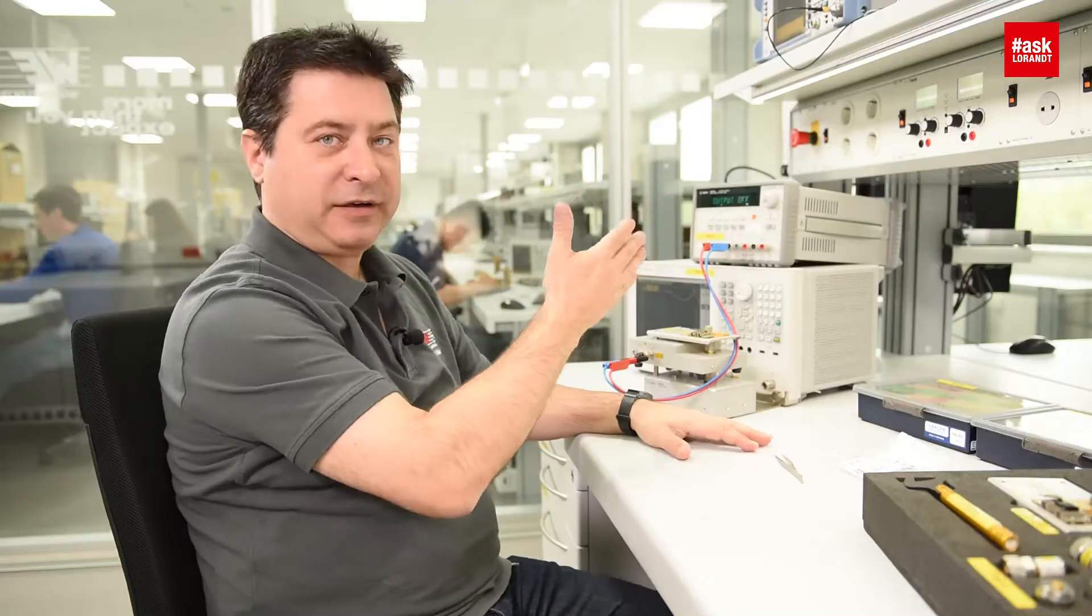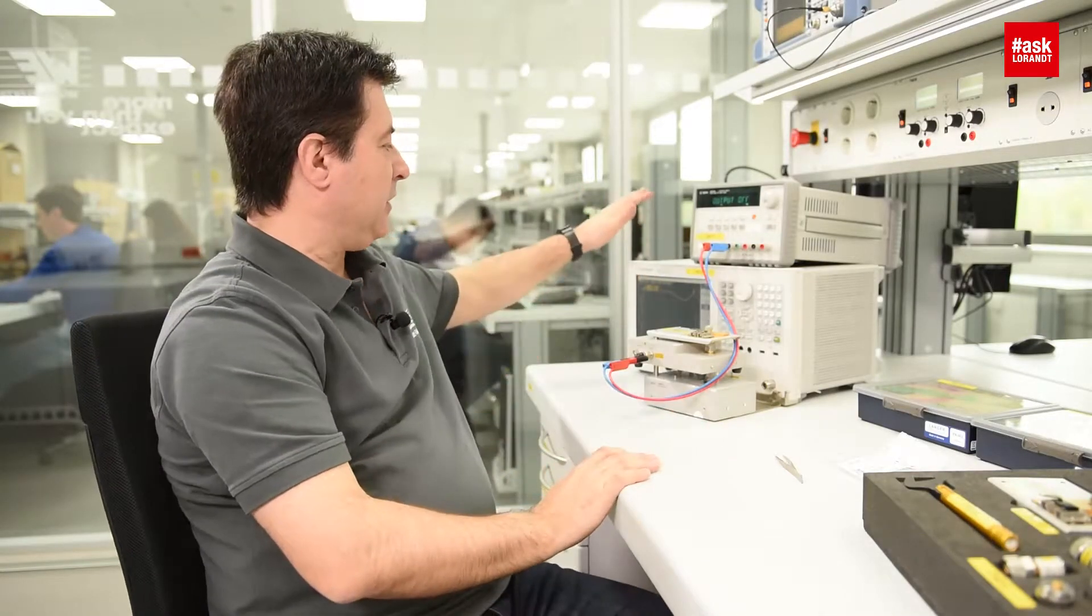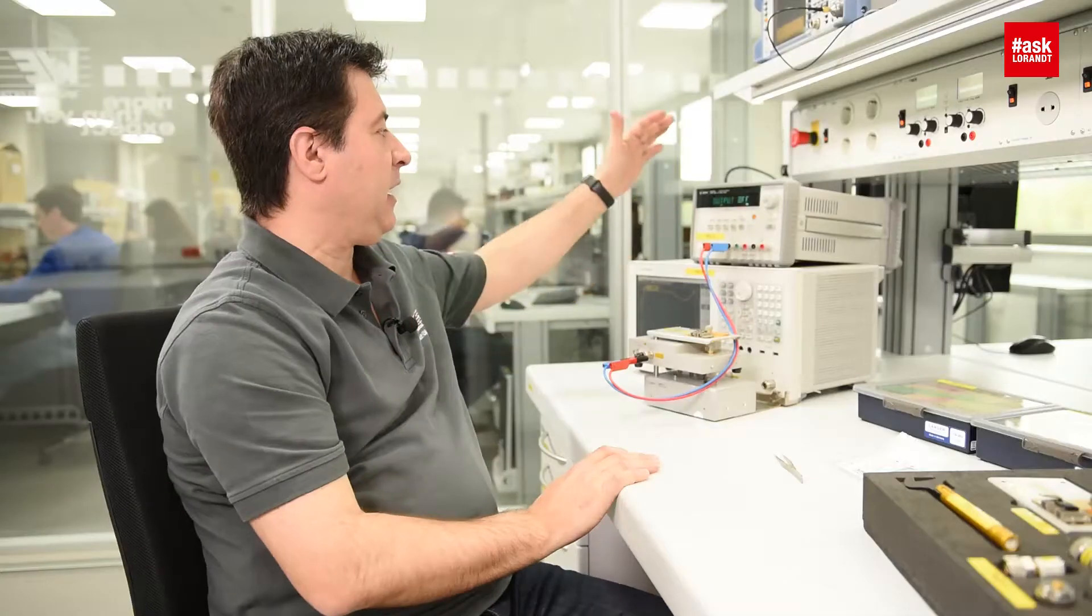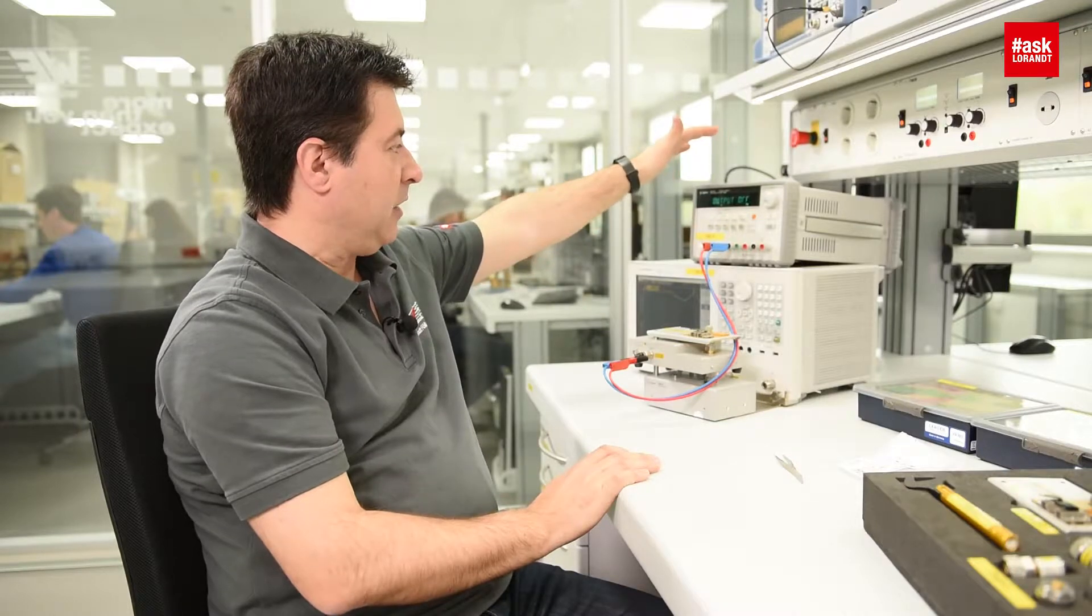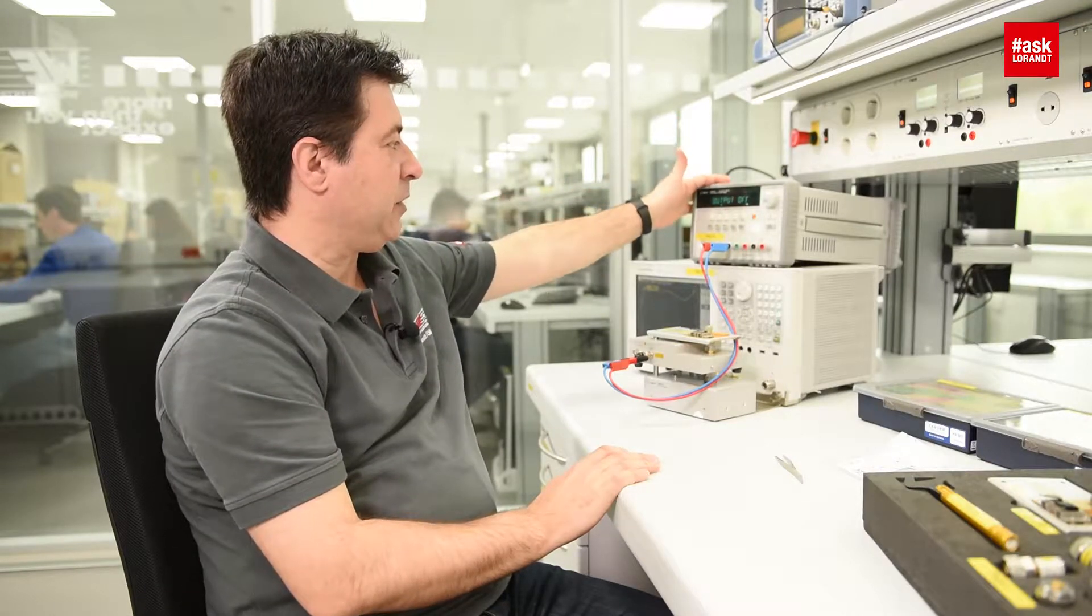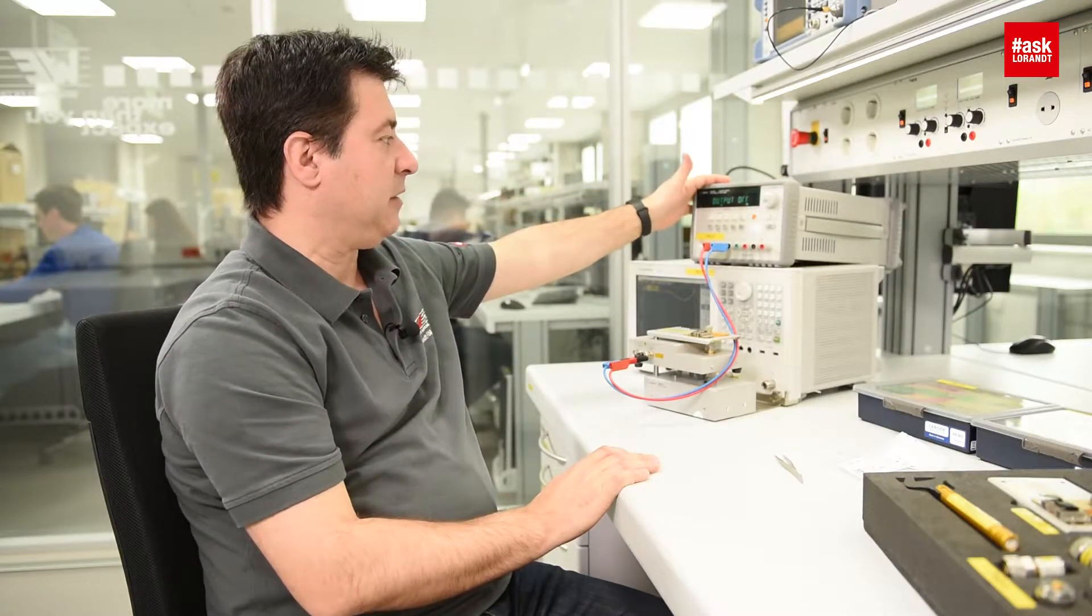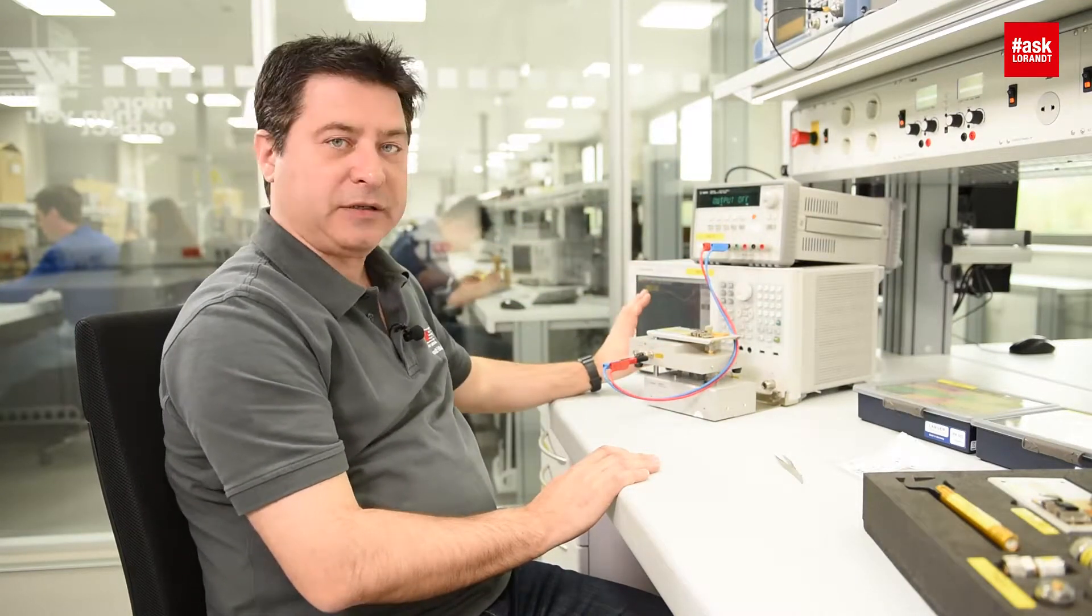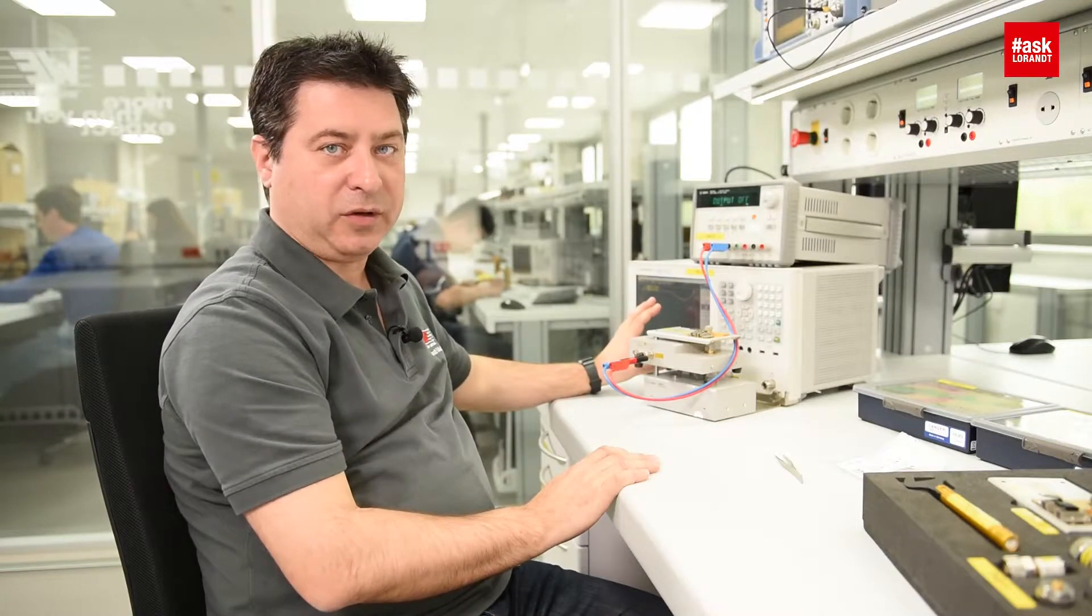For that purpose we have here an Agilent analyzer, it's a special network analyzer with a fixture, a special fixture for DC bias load, and we have from Agilent as well a power supply, a laboratory power supply with precise output. We will give some DC bias load and we will measure the impedance with and without the load.